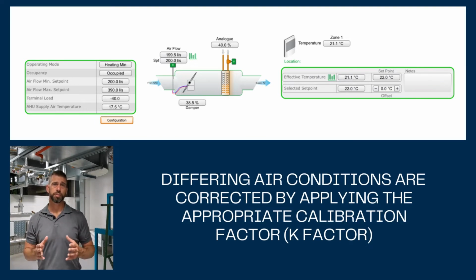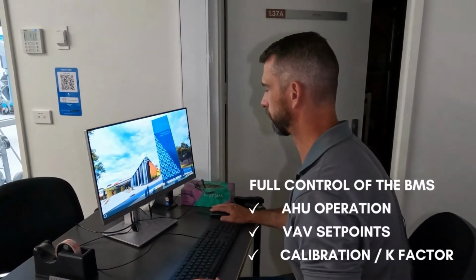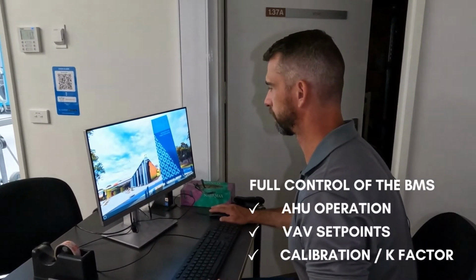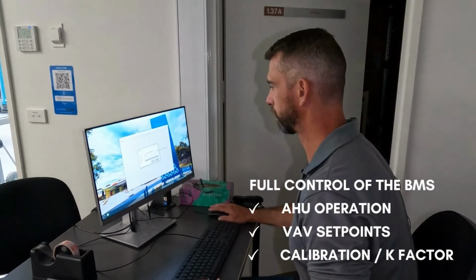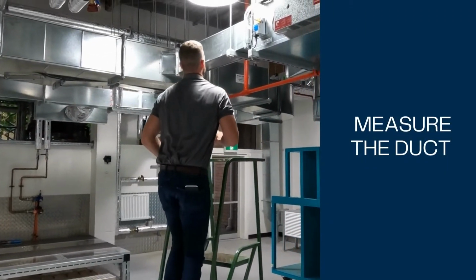It's vitally important that the BMS is a true reflection of the air entering that VAV box and therefore conditioning the space. This brings us to the importance of the BMS operation. It's important when you're calibrating a VAV box that you have full control of the BMS. Ideally, you want to be able to control the AHU operation, VAV set points, and of course the calibration or K factor.